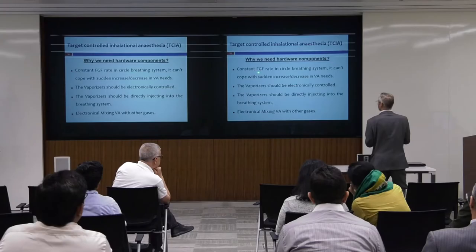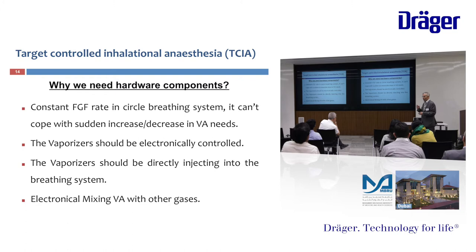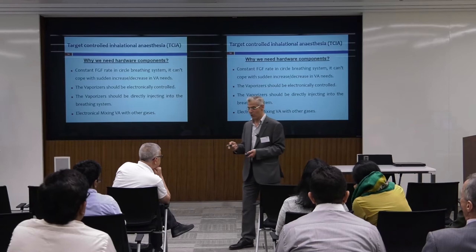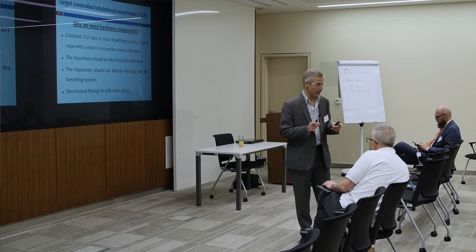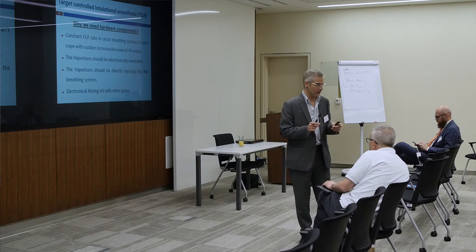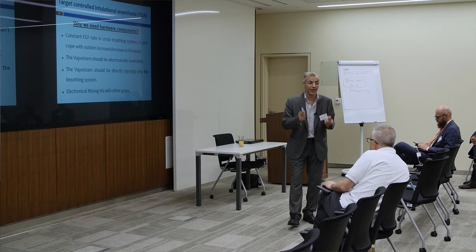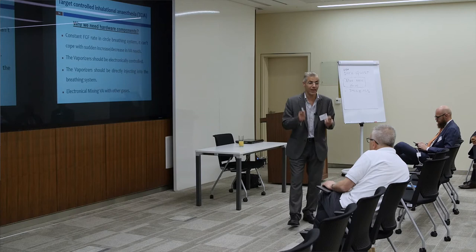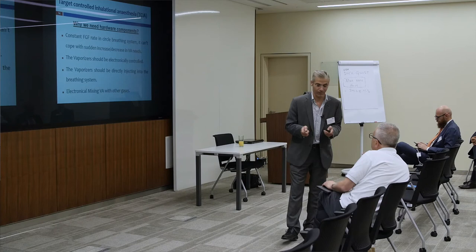Why do we need the hardware component? The conventional fresh gas flow rate and circuit breathing system cannot cope with sudden increases or decreases in volatile anesthetic need. This was a matter of discussion with Dr. Fawaz during the course, and he expressed some negative feedback — we couldn't find the reason. But the advantage of this machine is that it can compensate for any sudden change during the automatic gas control. The vaporizer should be electronically controlled, and because of this, we cannot have target-controlled inhalational anesthesia with any machine having a mechanical type of vaporizer.